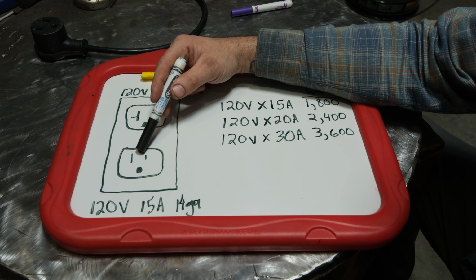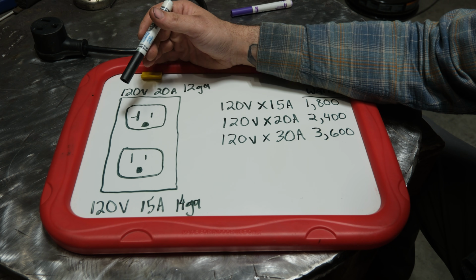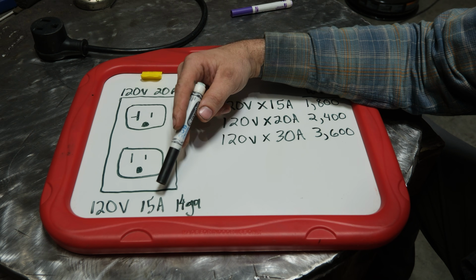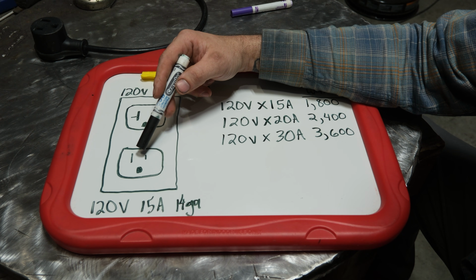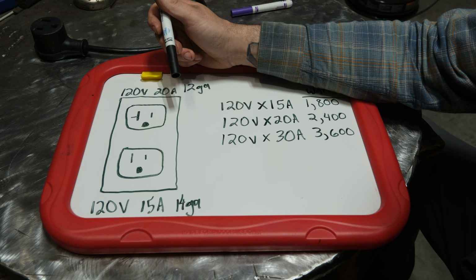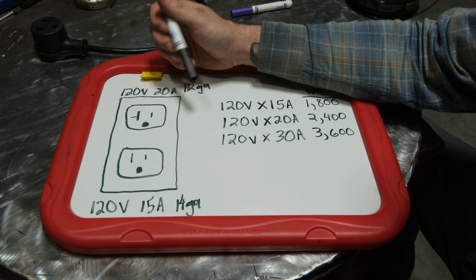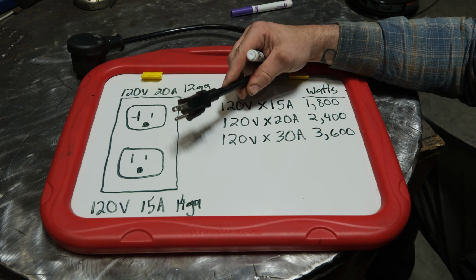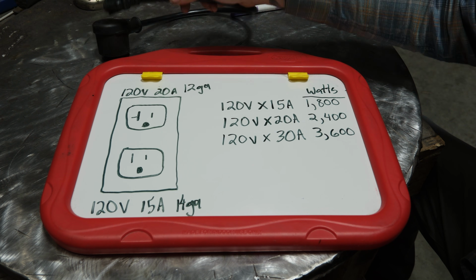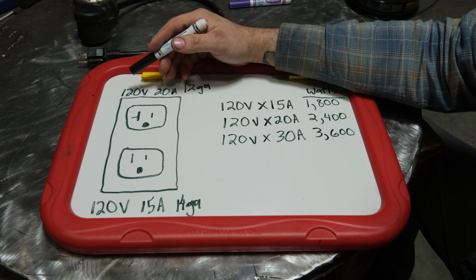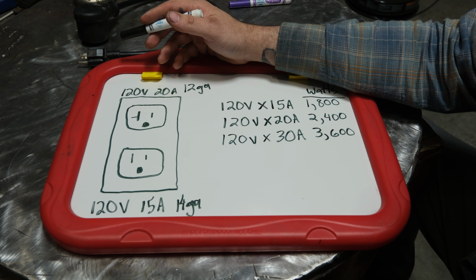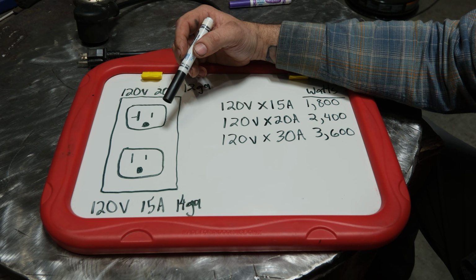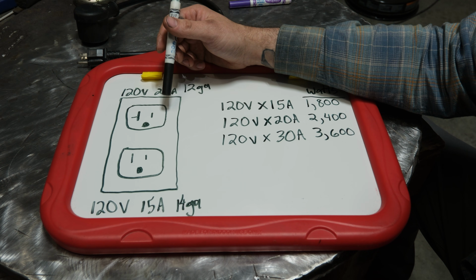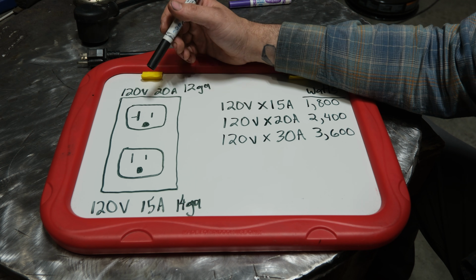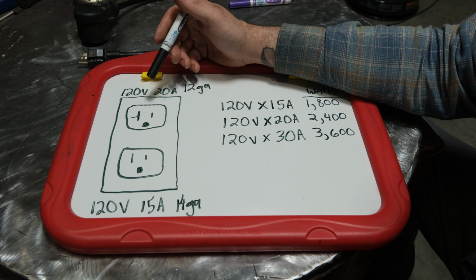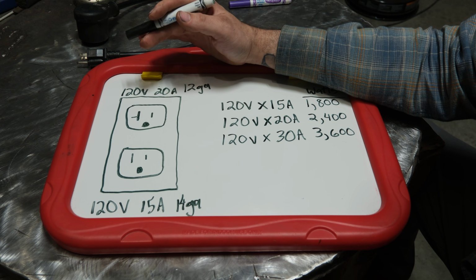If your outlet looks like this, you have what's called a 15 amp circuit. Now, that does not mean that you don't have a 20 amp breaker on that, but the outlet itself is really a 15 amp circuit. Now, if you notice, this has a 15 amp plug, which I've always found kind of ridiculous, since under no circumstances should a 15 amp outlet, if that's what the breaker rating is and that's what the wire size is, really be hooked to a welder of any kind. There simply isn't enough power there, but whatever, that's just how things are.